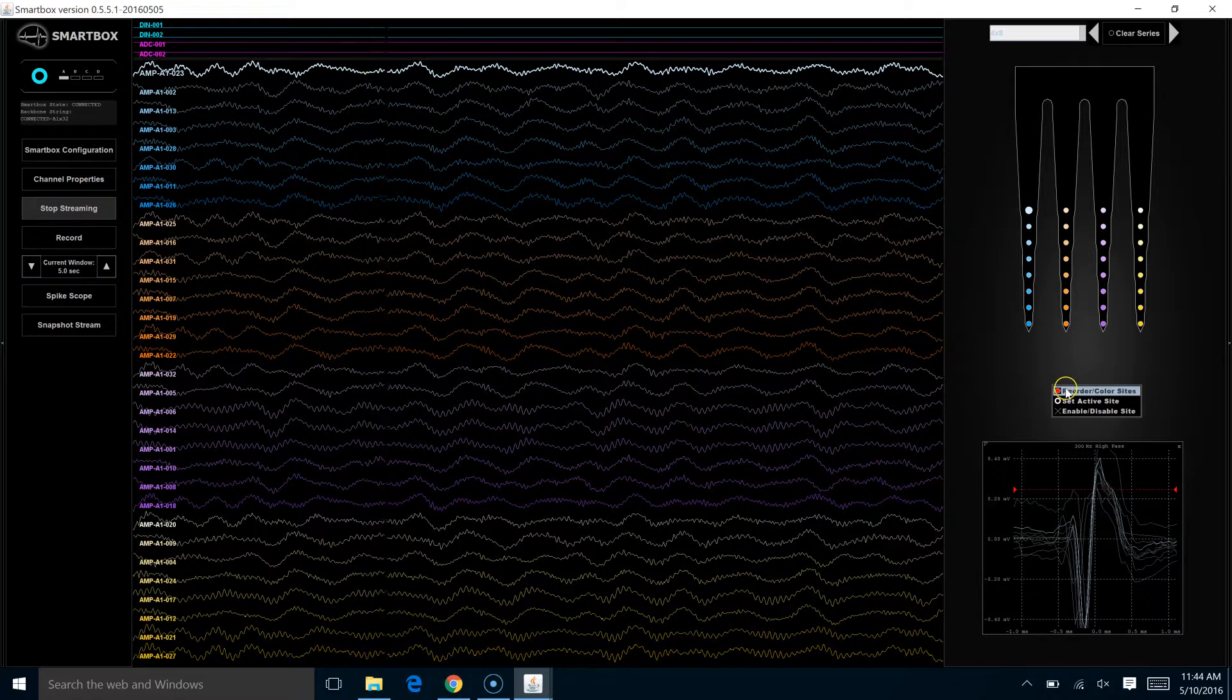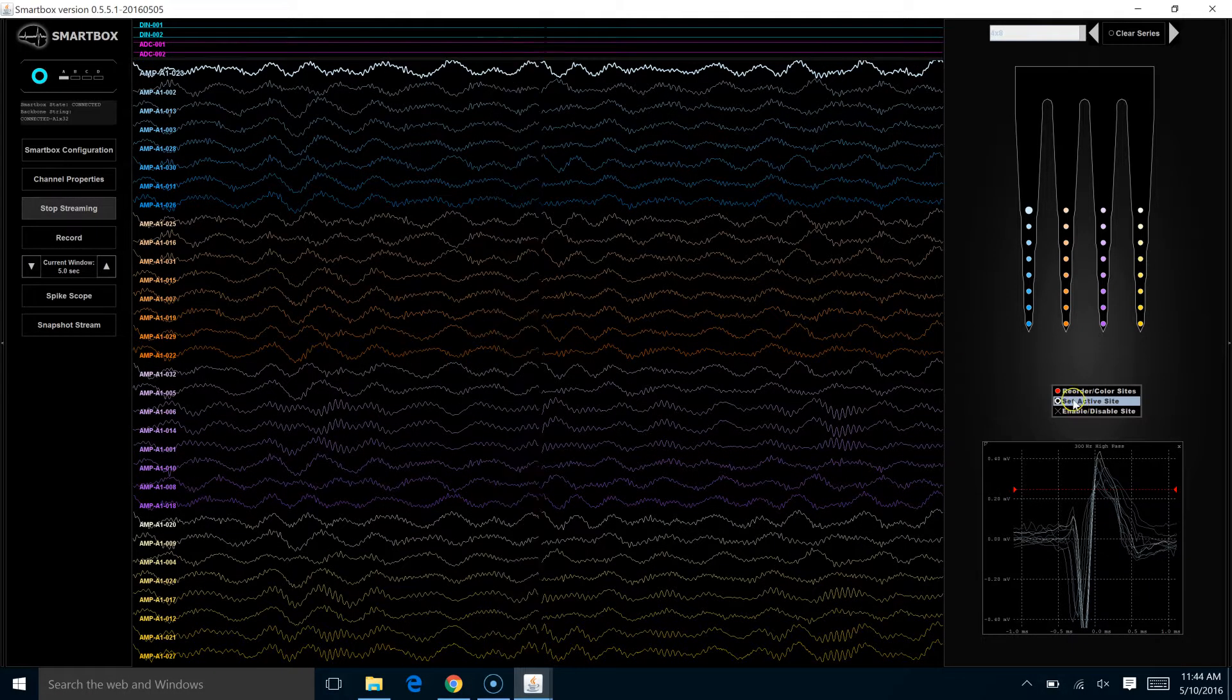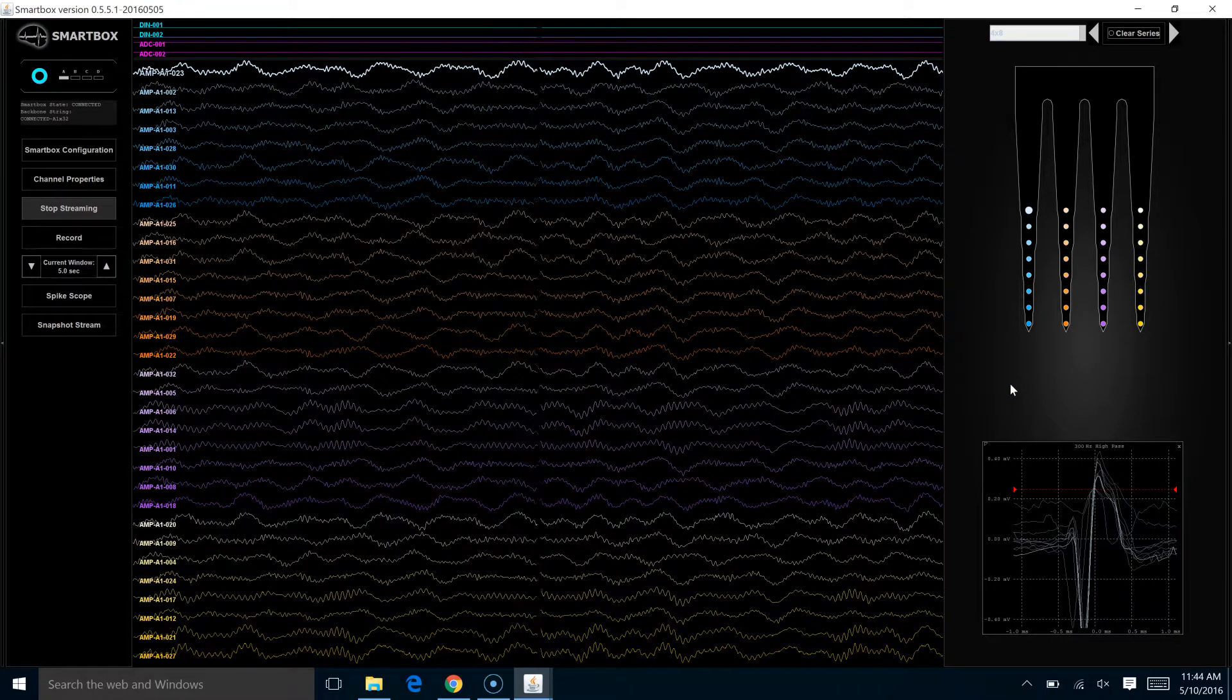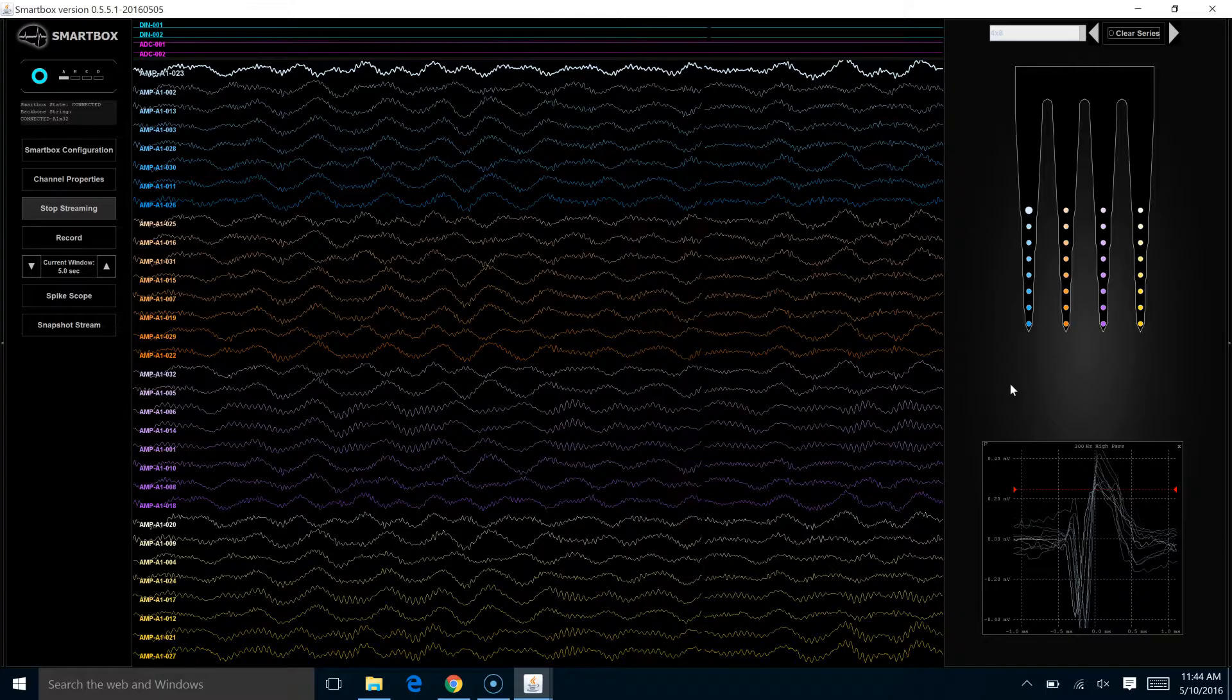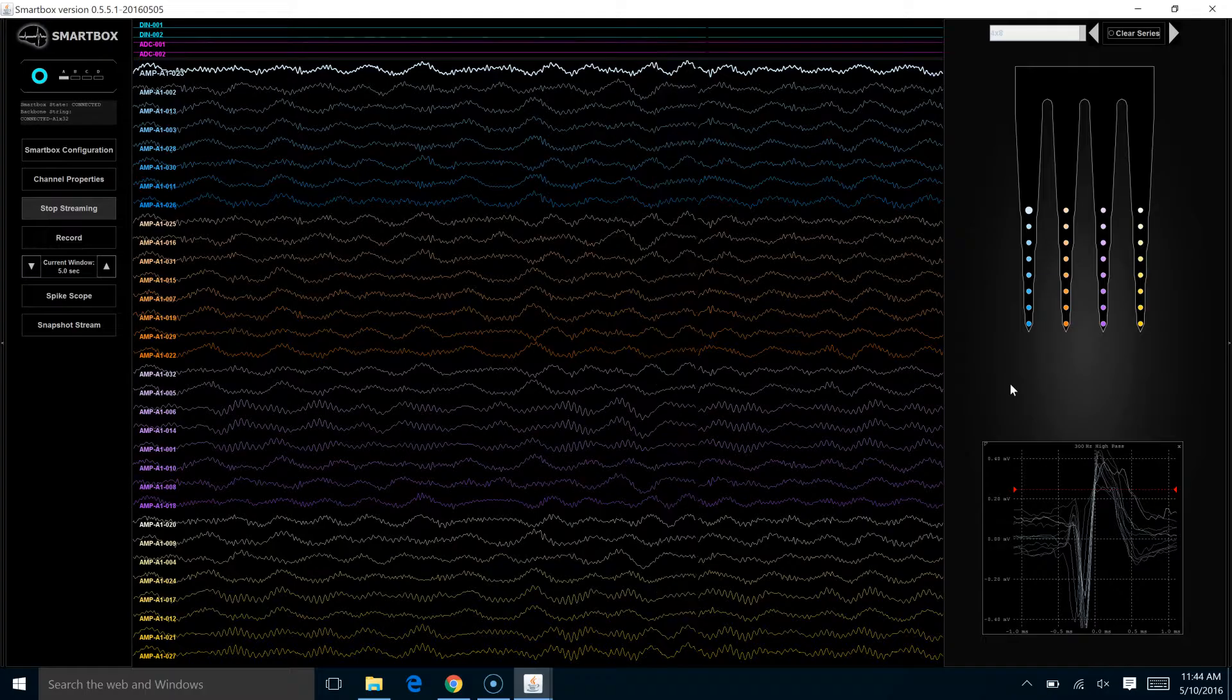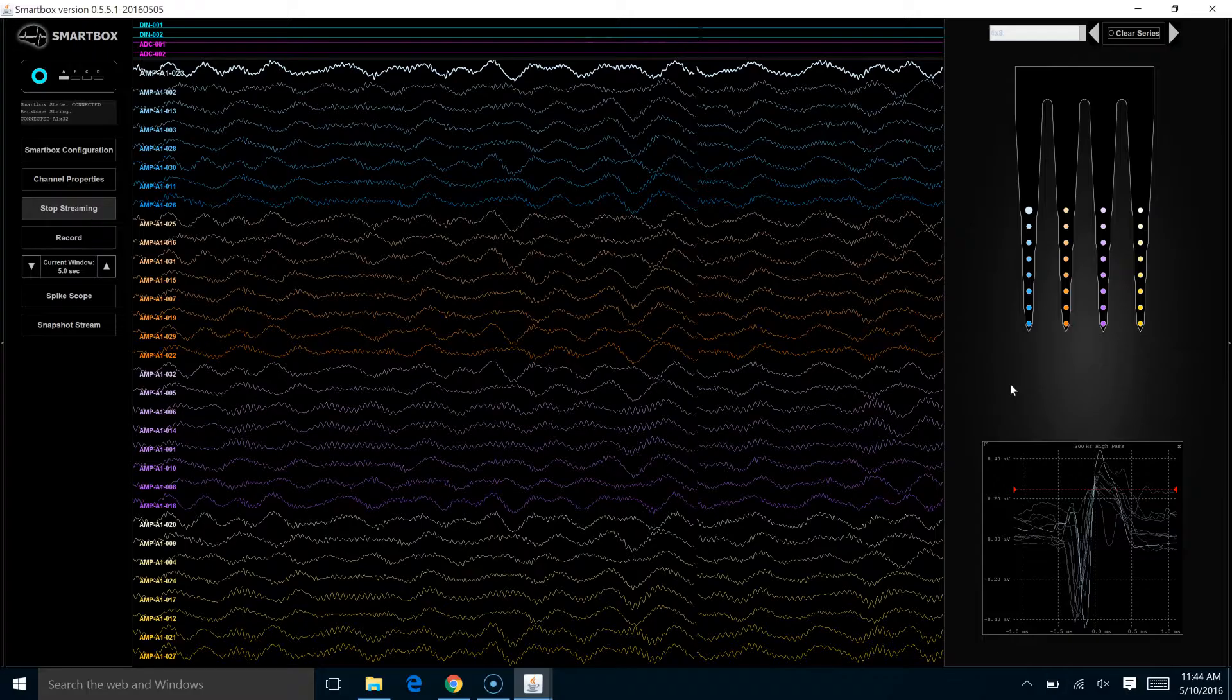If we right-click again, we see that the third option that comes up is enable or disable site. That option would be used if you are using a probe that you know has a bad site on it, or maybe it didn't have a bad site when it went in, but maybe there's just a lot of noise on that particular channel, and it's distracting you from the channels that are of interest to you.